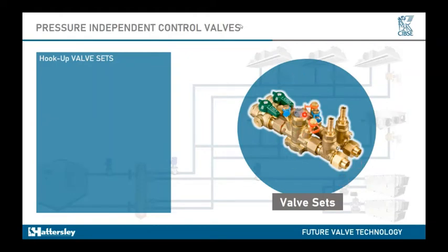You've got various different test points which can do various items like checking your minimum activation and you've got enough pump pressure within your system, checking your flow rate, and the combination of several test points like the blue and the red here can then give you the DP across your coil as well, so you can see if there's no blockages. But as I say, there are various different variances on the market. These all have different variants within the product ranges as well, but again, it's just something that you can speed up the installation of your building and projects.